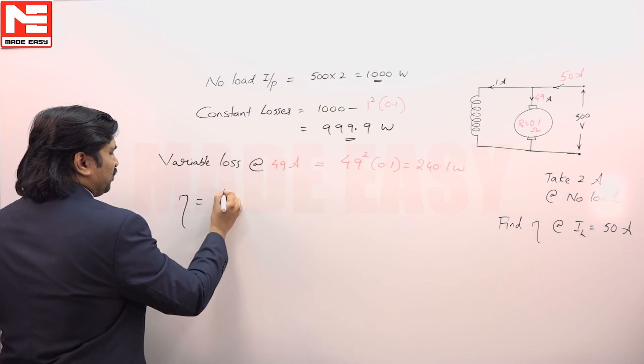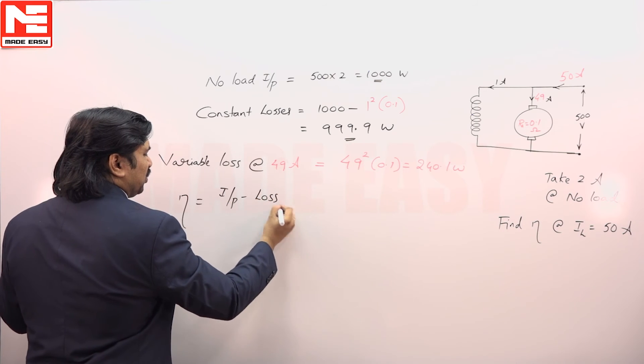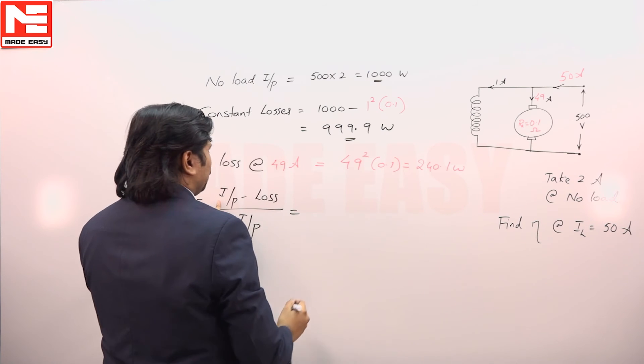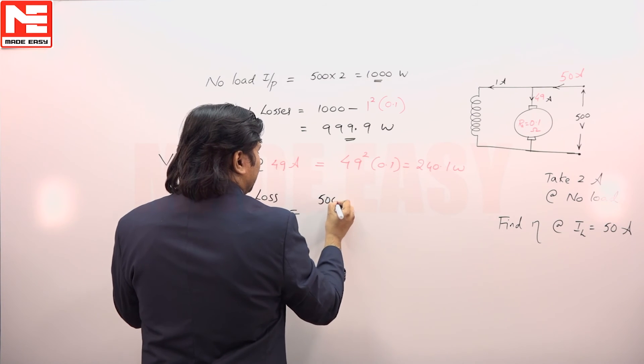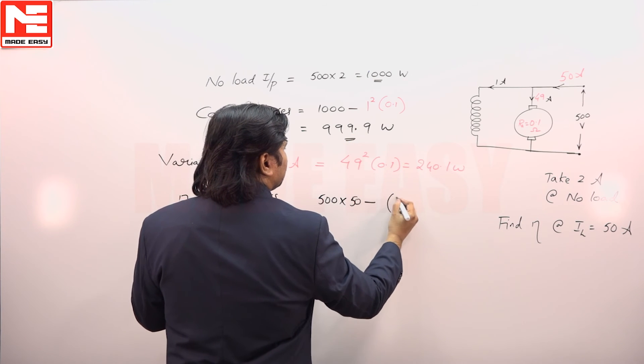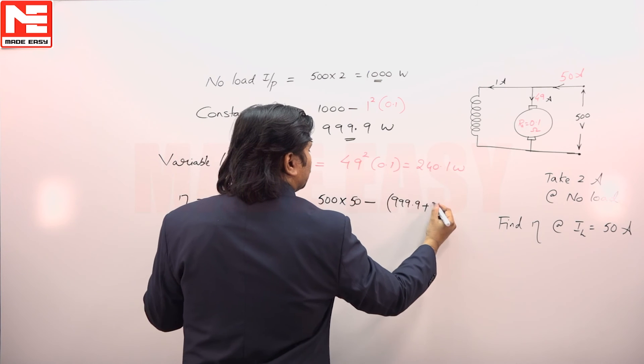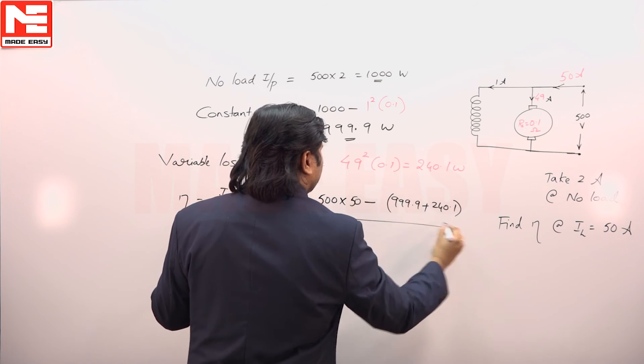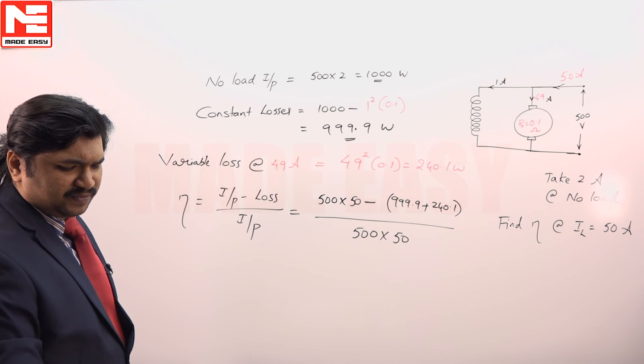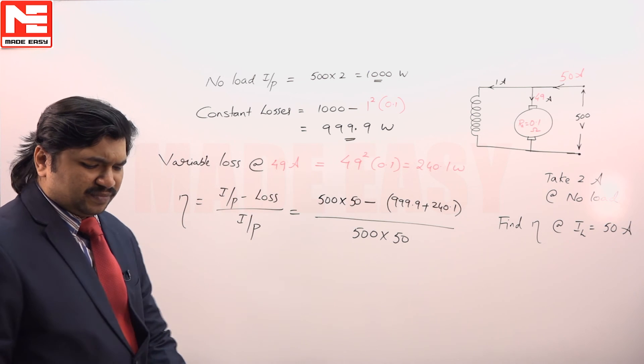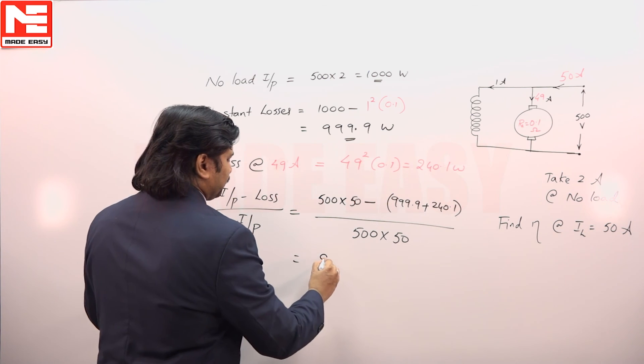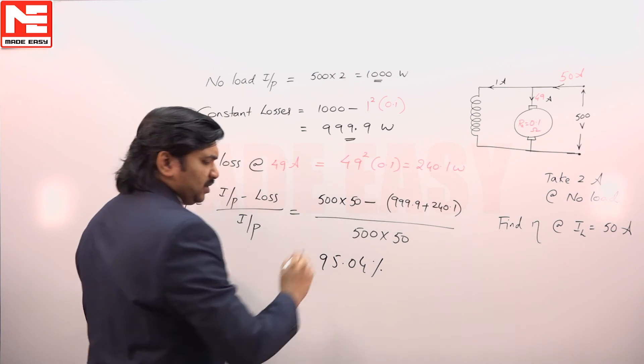Efficiency is equal to input minus loss by input. It is convenient to have a motor because input is V into I L. So, what is input of the motor when it is run 50? 500 into 50 minus, what are the total losses? Constant loss plus variable loss by 500 into 50 A. It is 95 percent.